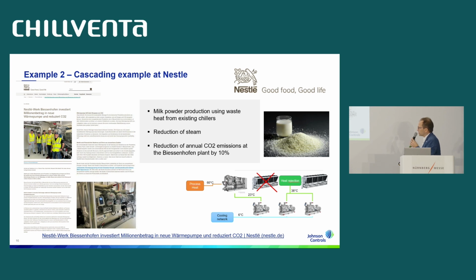So the process heat was provided for milk powder production using the waste heat. And before, steam was used for the milk powder production, we get rid of the steam. So a dramatic reduction of steam demand and reduction of CO2 emissions by 10% for the whole plant by only one installation. So a 10% reduction in annual CO2 emissions by only implementing one simple cascading heat pump. This is huge numbers, right? And if you want to have a look at that, please look on the Nestle webpage.